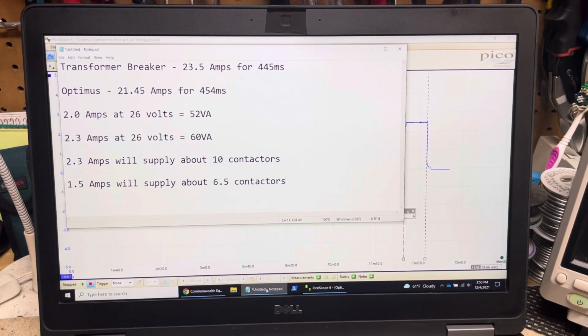The other thing is, it would be extremely rare on that circuit to have exactly 2.3 amps. It would have to be such a very rare, unique short that would provide exactly that amount of amperage, so that Optimus is allowing that through the circuit long enough to smoke a 40 VA transformer. What kind of residential or light commercial circuit would really be supplying 2.3 amps of load?